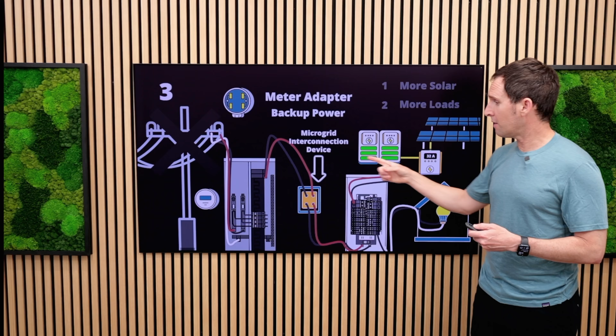You've got to pull out all the wires from the existing electrical panel. You have to make sure that when you pull out those wires, you don't strip them on the edges. Sometimes these are in very tight spaces. Then you have to install a new electrical panel and basically rewire it with all of the existing circuits.